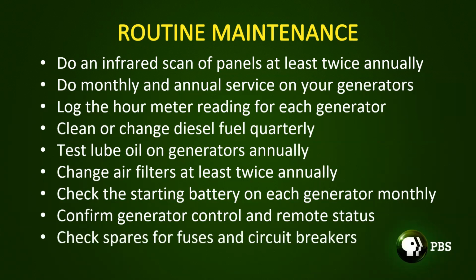And by the way, this is another one of those you learn by experience. Be sure to check your spares for fuses and circuit breakers, because as I mentioned, circuit breakers wear out, and you're not going to find a 1600 amp circuit breaker at your local electrical supply house, unless they have an industrial client that keeps those kind of things. It's just like trying to find one of these. This is a 1000 amp fuse. And once again, you're not going to find that at Home Depot or your local supply house sometimes. So you better have spares when you need them.